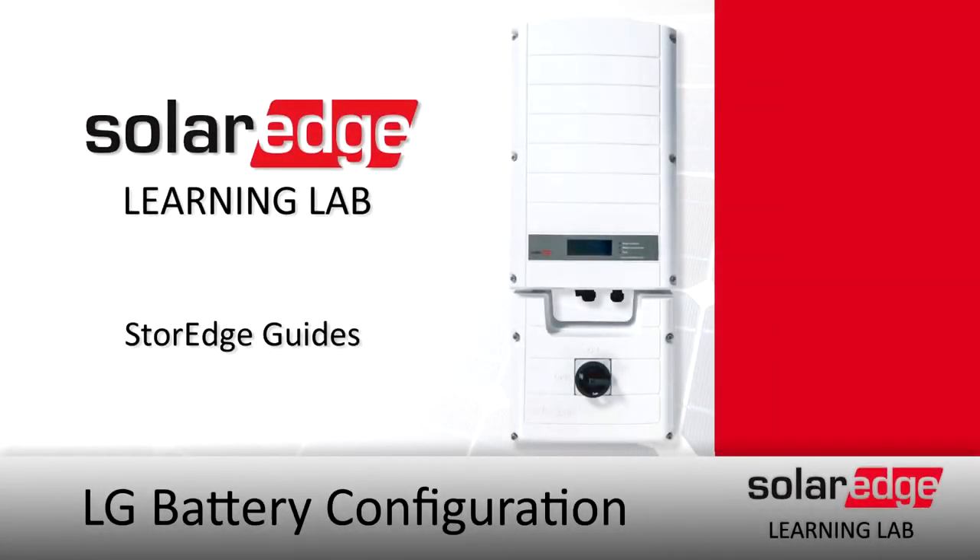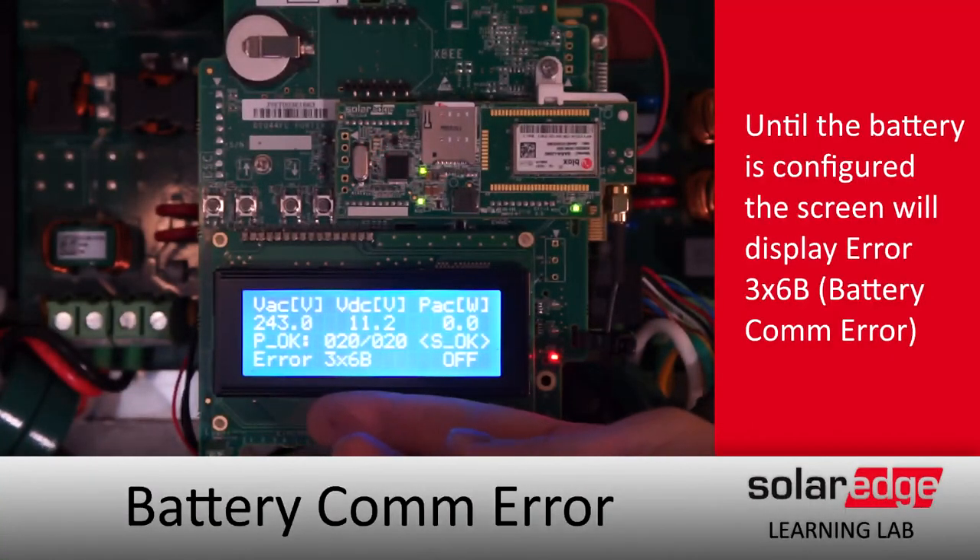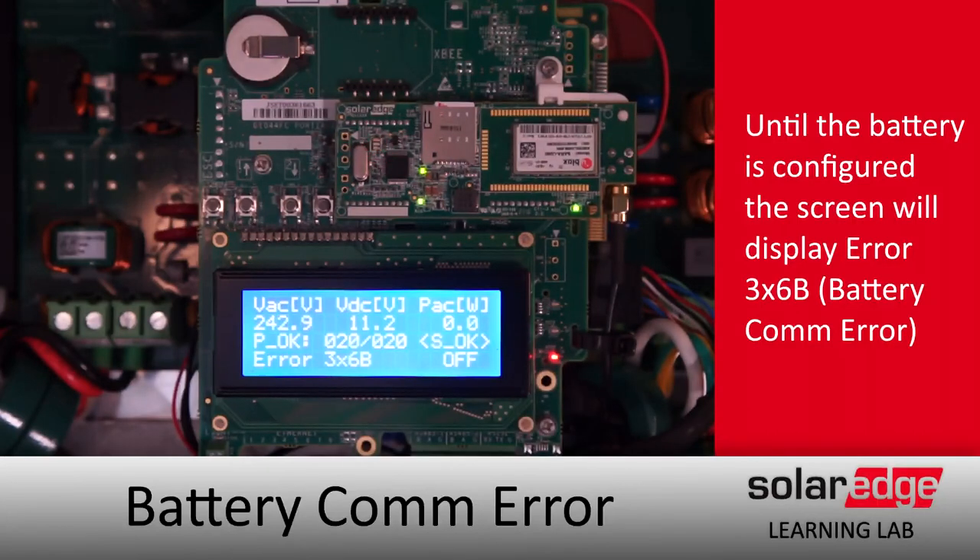We've got a brand new StorEdge installed today. As you can see at the bottom of the screen, we've got a 3x6 bravo error being displayed — that's a battery communications error. We need to set up our battery.